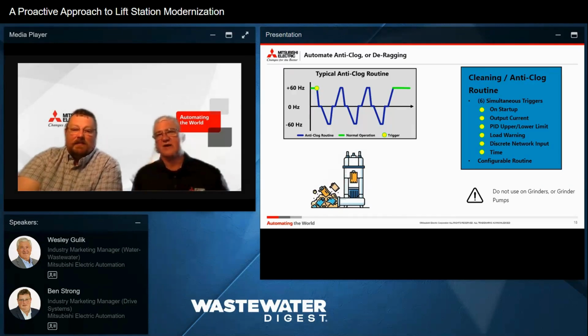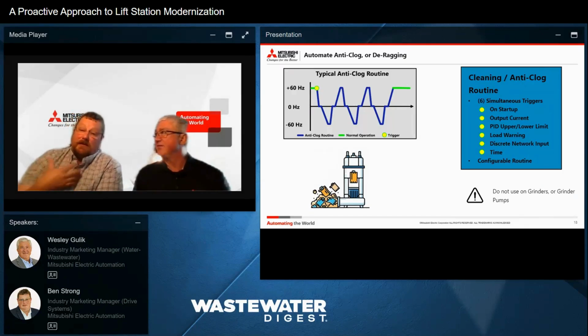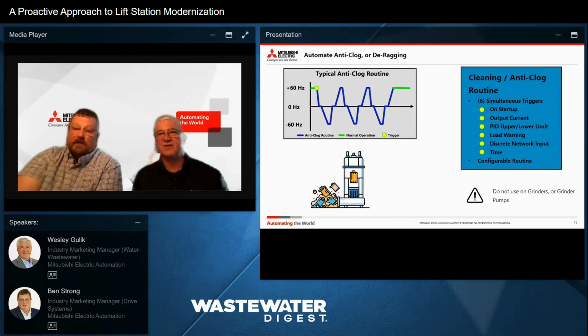The thought going through my mind is, with manufacturers, how easy or how difficult is it to set up these cleaning anti-clog routines, as an example? Are we talking a half a dozen functions, or 1,000 lines of PLC code? Now, with the VFDs that we use, it's one parameter. You enter a number, it represents the number of triggers and what types, and away you go. Very easy. It's one or two parameters. It's pretty clean.